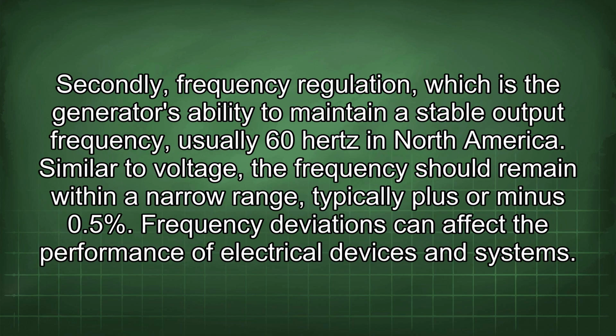Secondly, frequency regulation, which is the generator's ability to maintain a stable output frequency, usually 60 Hz in North America. Similar to voltage, the frequency should remain within a narrow range, typically plus or minus 0.5%. Frequency deviations can affect the performance of electrical devices and systems.